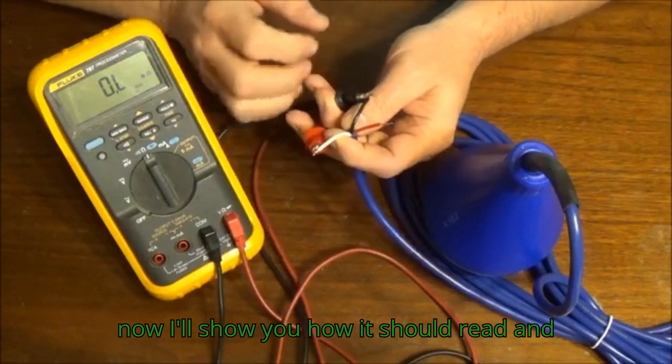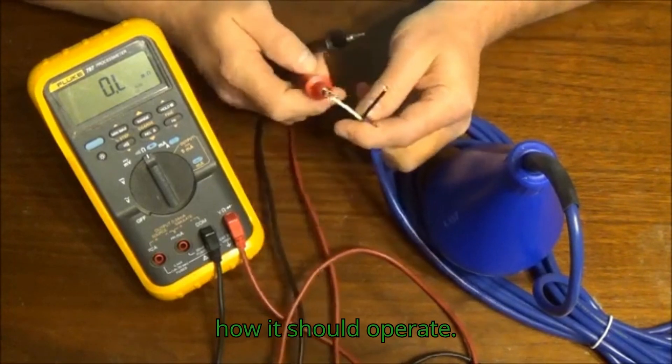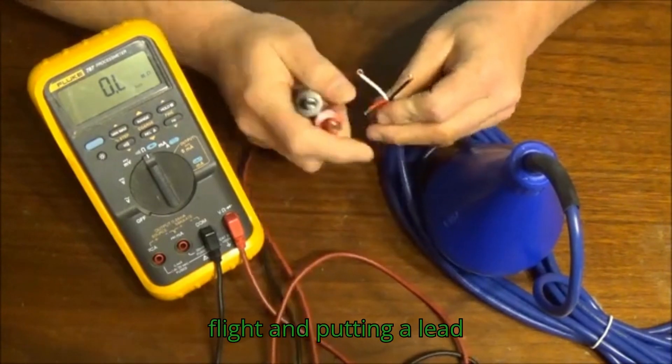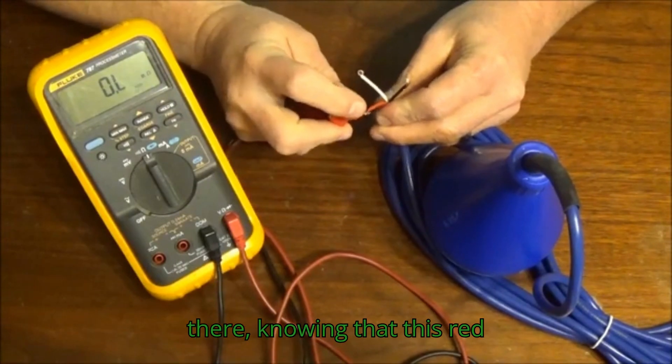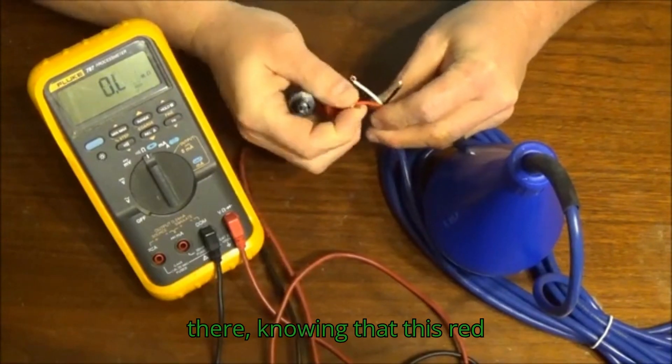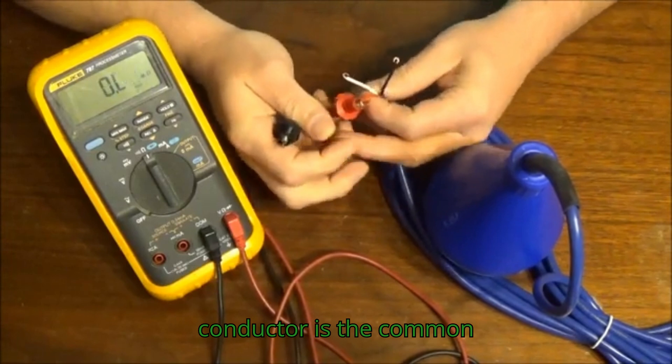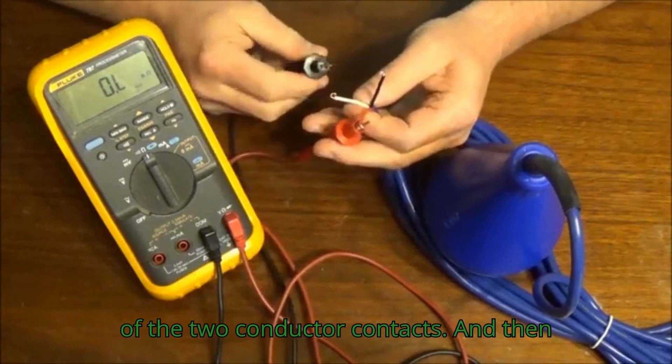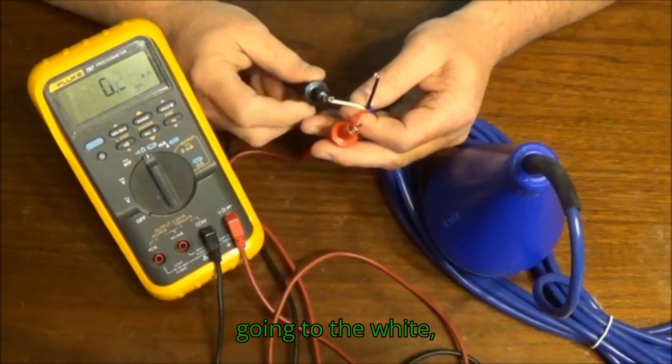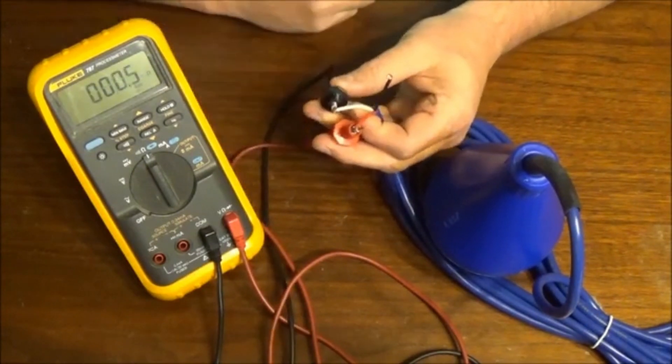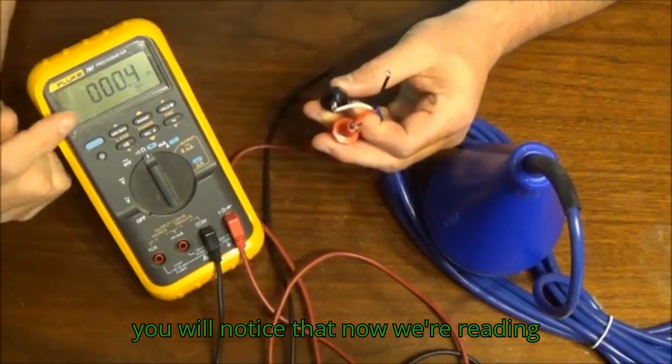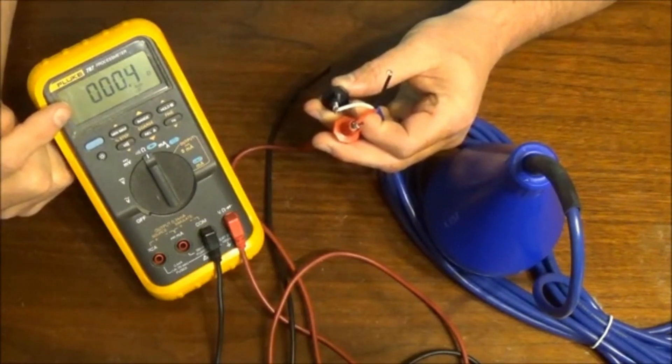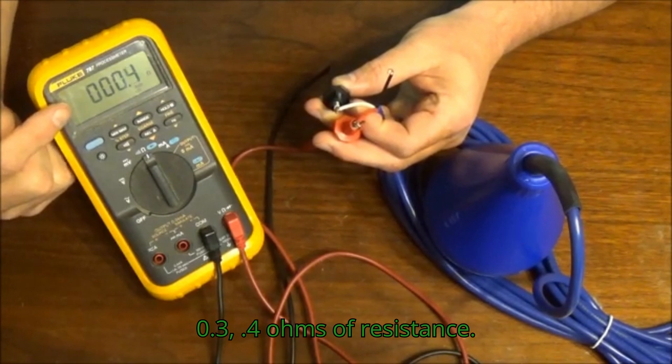Now I'll show you how it should read and how it should operate. Moving to this red conductor on this float and putting a lead there, knowing that this red conductor is the common of the two conductor contacts, and then going to the white, you will notice that now we are reading the shorted condition near zero, 0.3, 0.4 ohms of resistance.